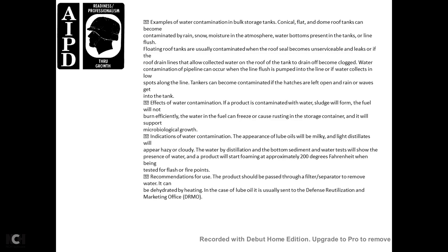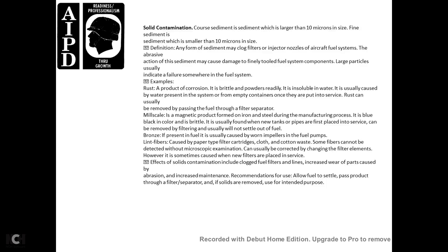Indications of water contamination: lube oils will appear milky; light distillates will appear hazy or cloudy. The water distillation bottom sediment and water test will show presence of water. Product will start foaming at approximately 200°F when beginning flash or fire point tests. Recommendation: the product should be filtered or separated to remove water, or dehydrated by heating. In such cases, lube oil is usually sent to the Defense Reutilization and Marketing Office (DRMO).